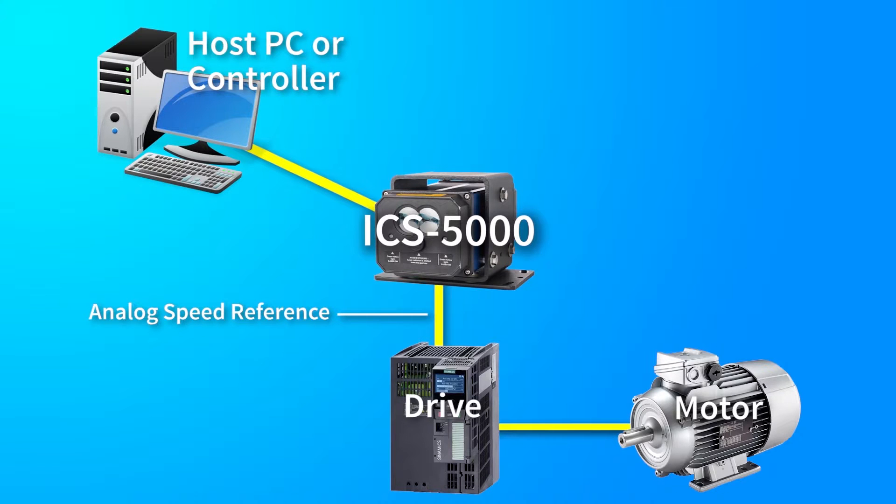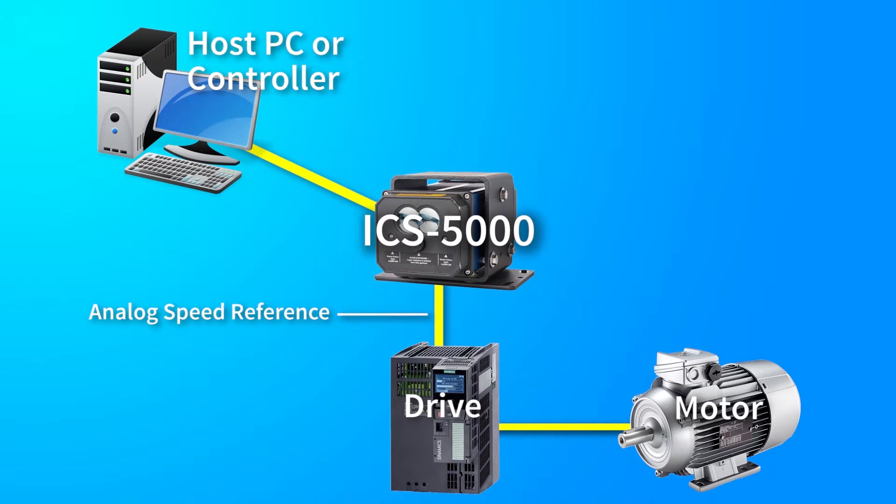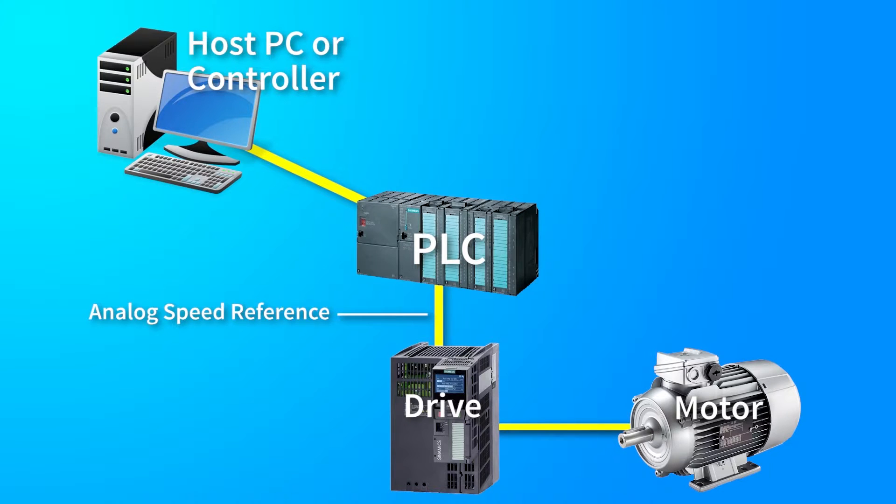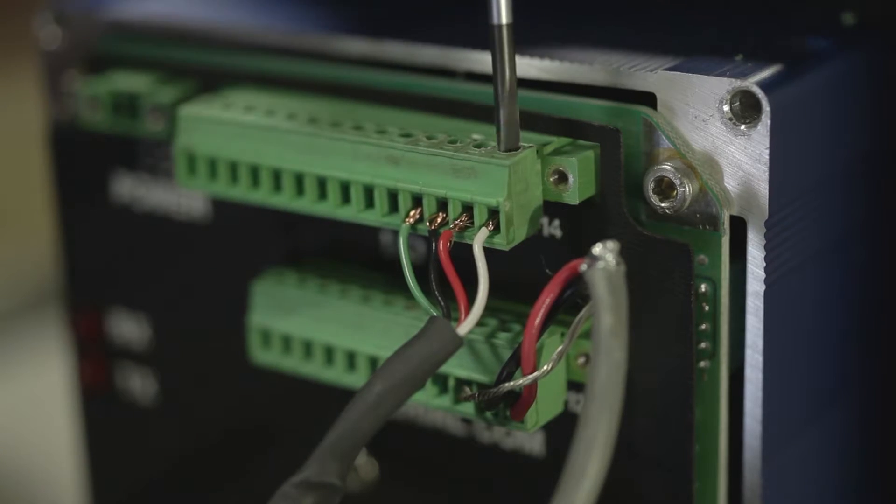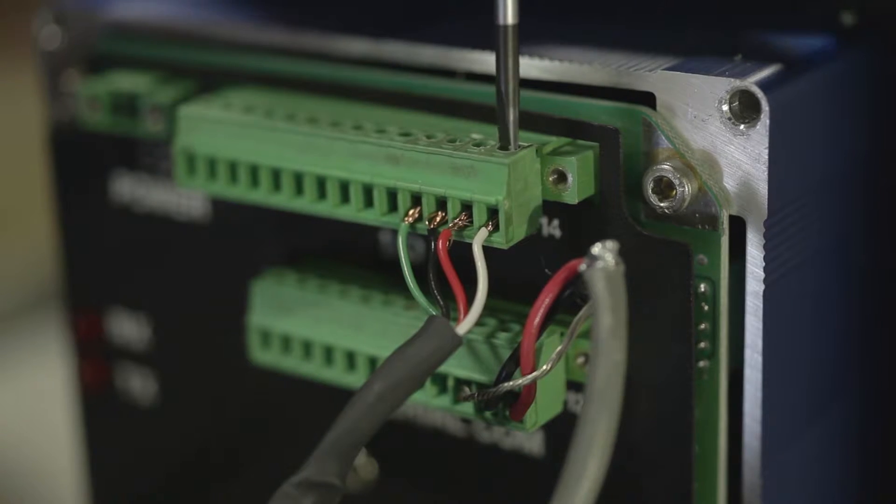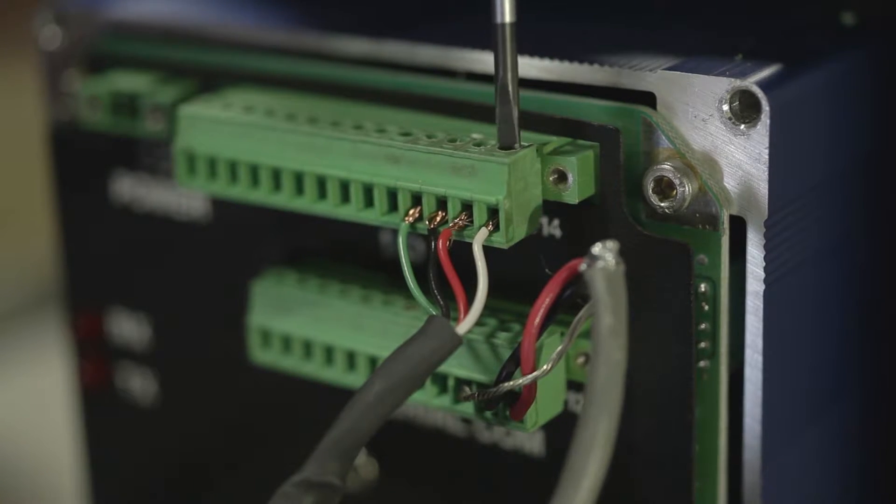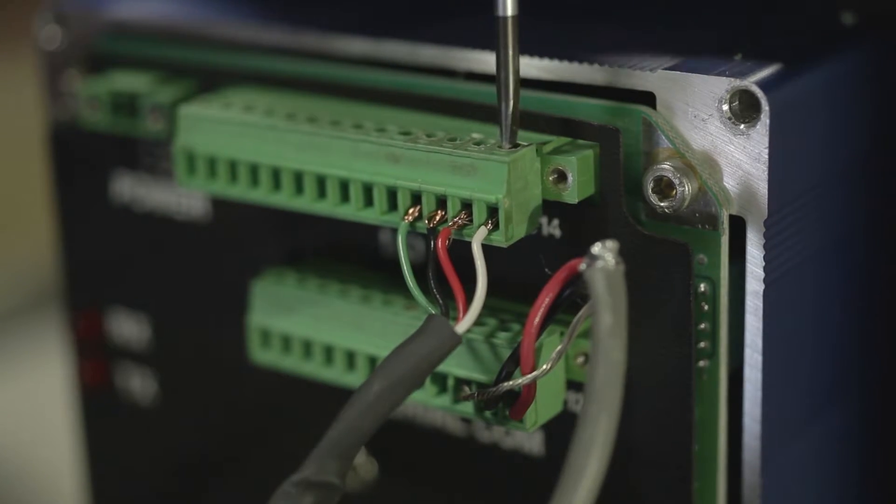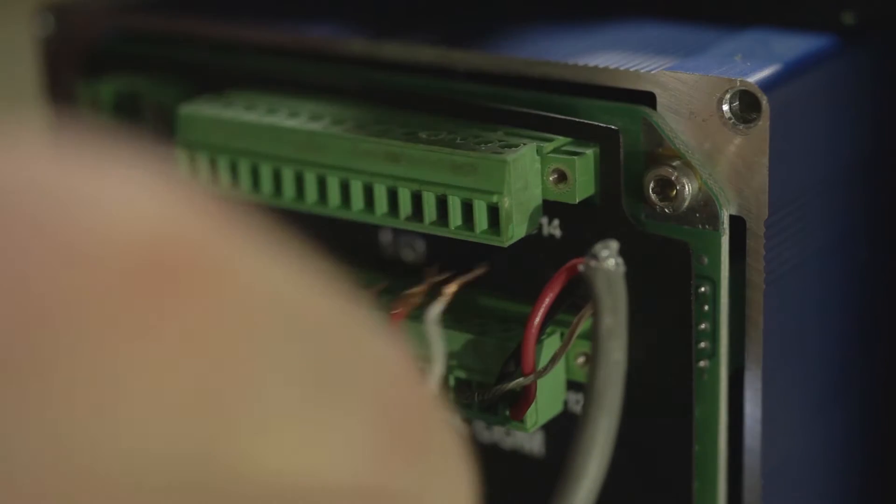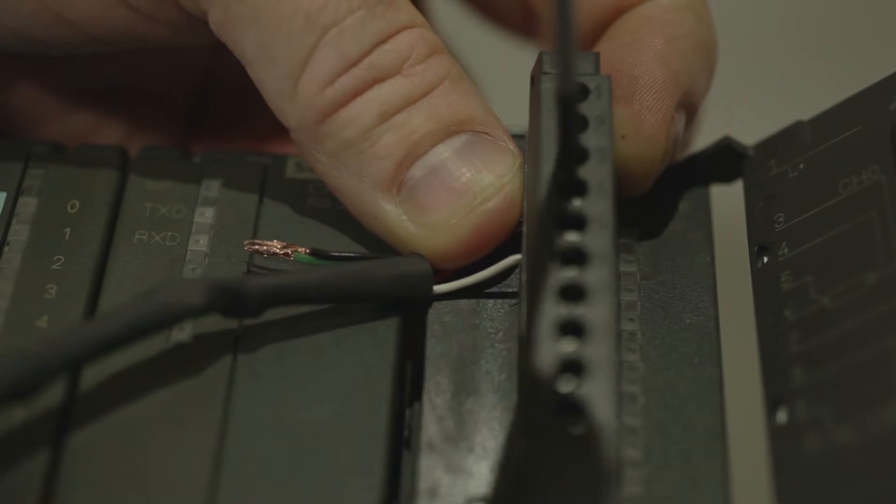An analog velocity signal to the motor drive allows the ICS to control the speed of the main motor on the crane or vehicle. In the converted system, the motor's speed reference from the ICS is replaced with closed-loop position control inside the PLC. The installing technician moves the analog velocity command signal wires from the ICS analog output to a similar analog output on the PLC.